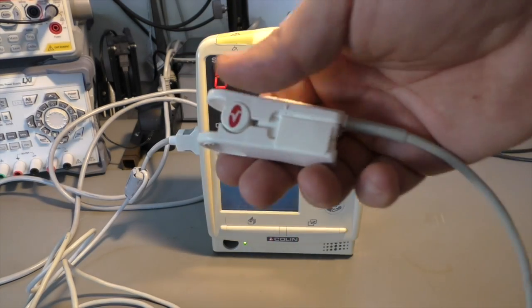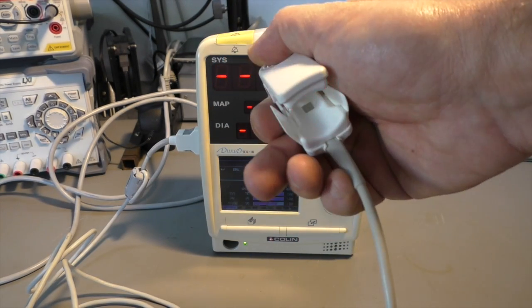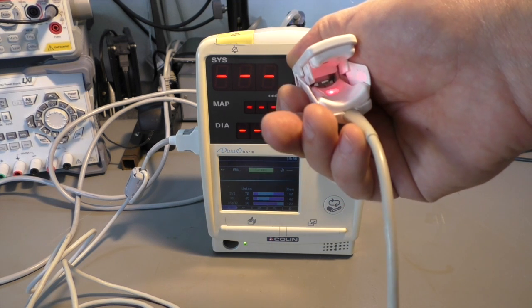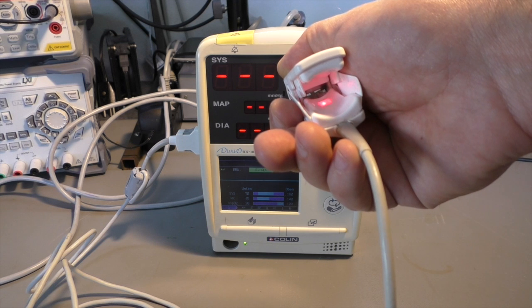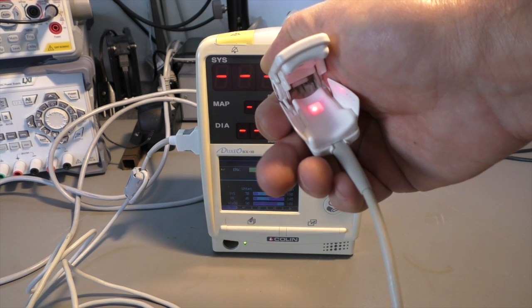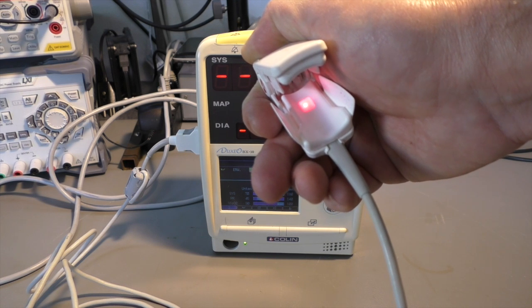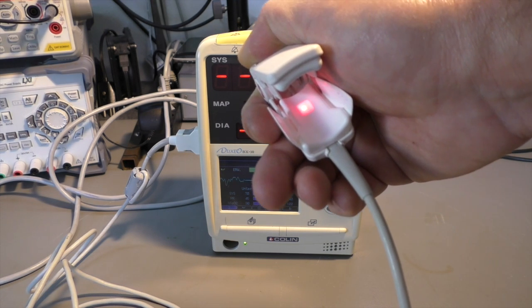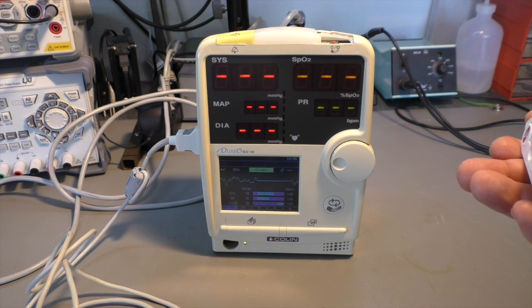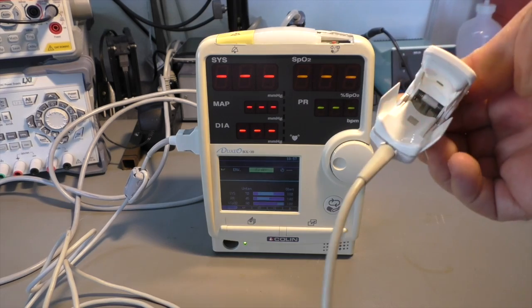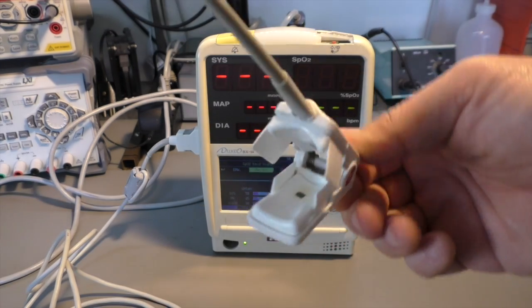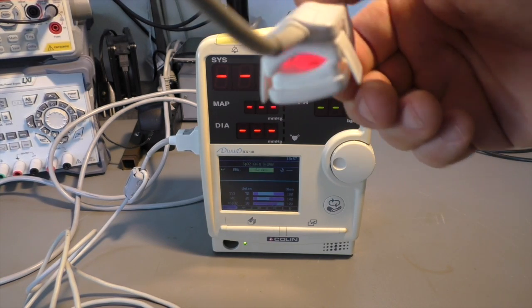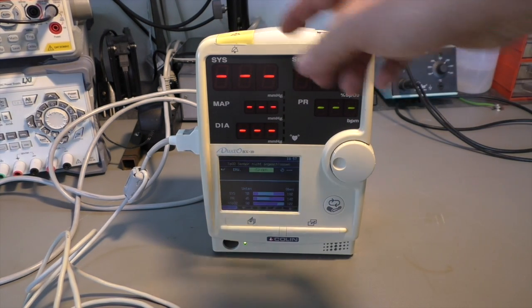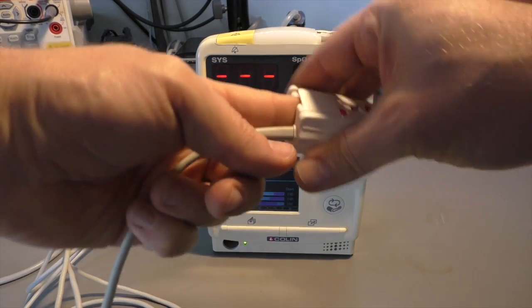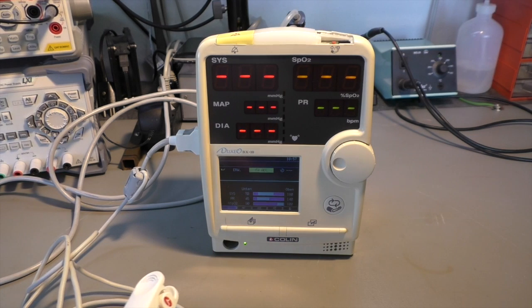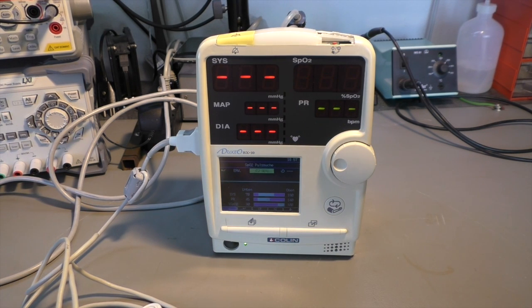Maybe if I switch the light off a bit. Yeah, here you can see the red LED. You can probably see different colors, different wavelengths, different intensities. So the unit tries to find a finger. Oh, we actually had a reading there, which is of course wrong. And then on the other side of the clip there is a little square sensor array. Now it beeps because something is wrong with the sensor, so I put my finger in. Light goes through my finger. It doesn't hurt at all.